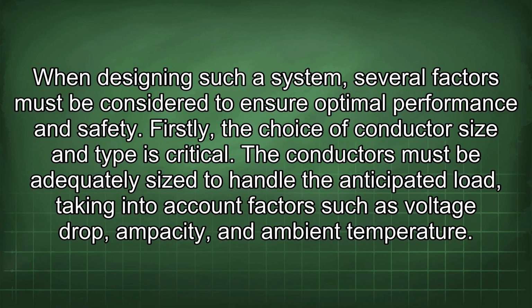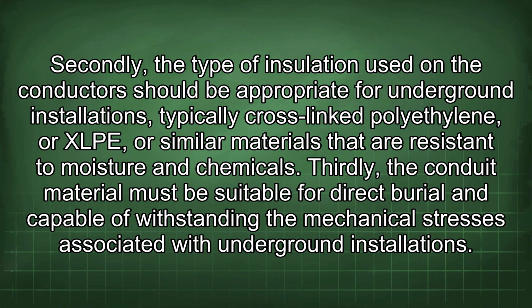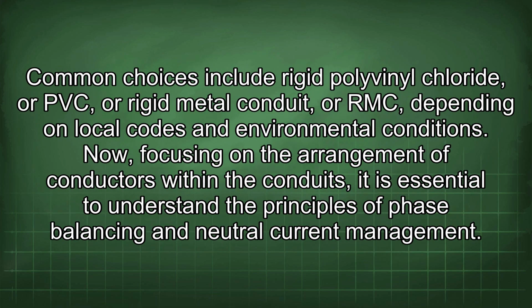and ambient temperature. Secondly, the type of insulation used on the conductors should be appropriate for underground installations, typically cross-linked polyethylene, or XLPE, or similar materials that are resistant to moisture and chemicals. Thirdly, the conduit material must be suitable for direct burial and capable of withstanding the mechanical stresses associated with underground installations.